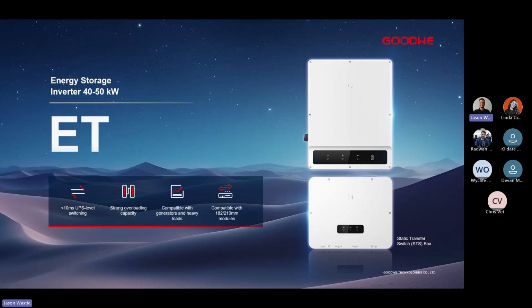So our grid connection comes into the static transfer switch. We will then be able to distribute that power either to our backup loads, or from our generator into our backup loads, or from the inverter through and into our backup loads. I'll explain it in a little more detail as we go through the presentation today. However, that's the basic concept of our inverter: we've got a DC-AC converting hybrid inverter, and with the STS separate, we do all of our switching. So it is theoretically an on-grid inverter with a backup port and a battery port, and if we add the STS, we get a full hybrid solution.